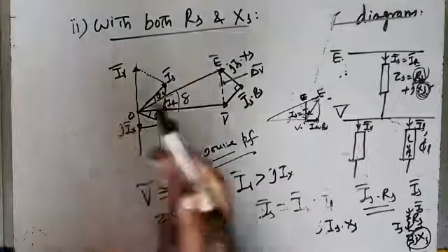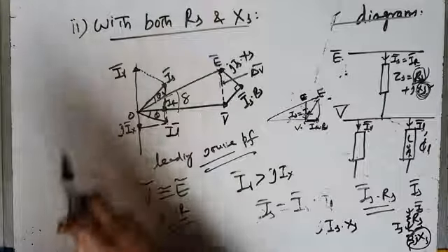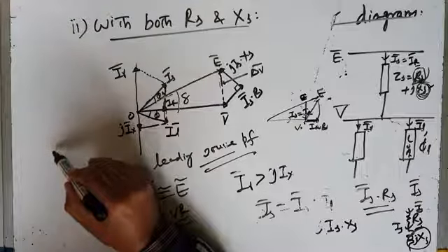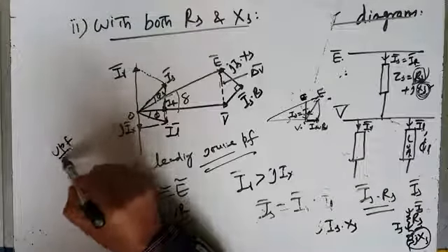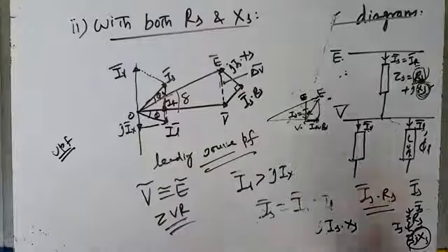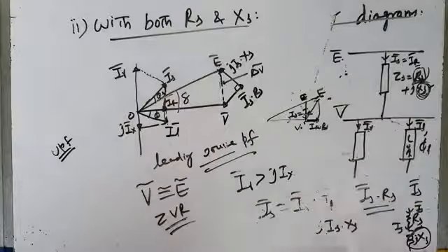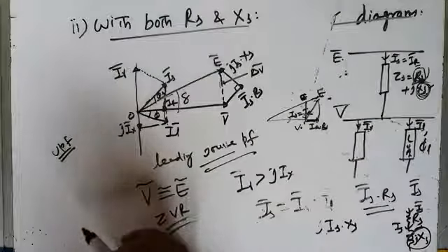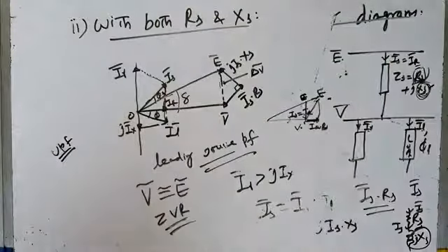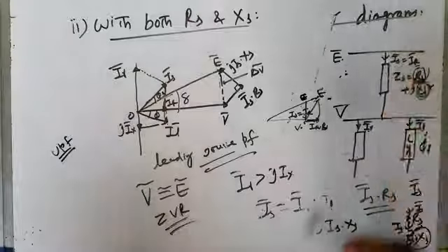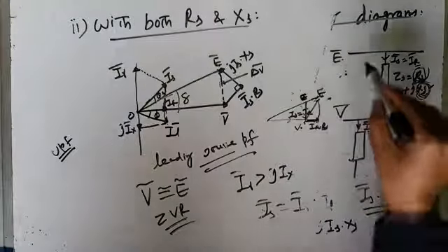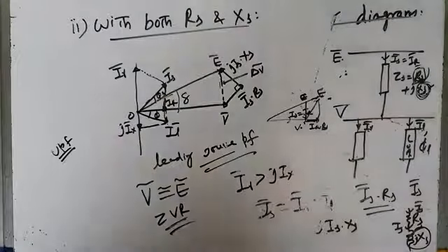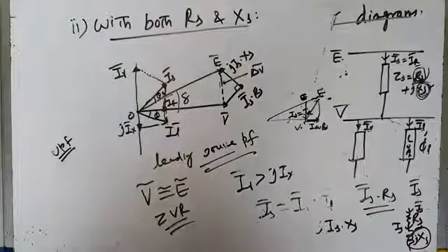In my opinion, we should use it as a power factor corrector for unity power factor operation, because for unity power factor operation the compensator has to compensate only load reactive power, so its rating will be less and source power factor will be unity.